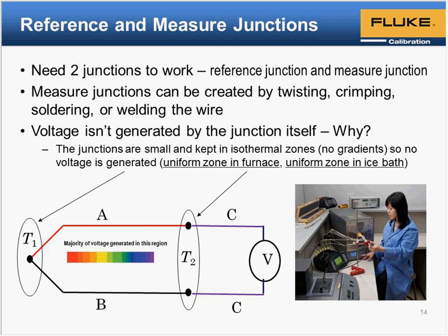So eventually you either have to connect copper wires that you can then take to your voltmeter, or you connect the thermal wire directly to the meter, but the wires touching connectors in the meter. What method you're using, whether it's copper wire or the wire is touching a copper connector in the meter, you need to know the temperature of T2. So we need to control T2 and identify what it is.